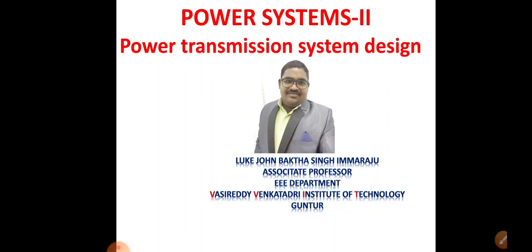Natural frequency voltage is the voltage which appears immediately after the sudden occurrence of a fault. It is simply added to the fundamental frequency voltage. So the main reason for transients in power systems is that inductors and capacitors are present in the system, and a switching operation takes place.